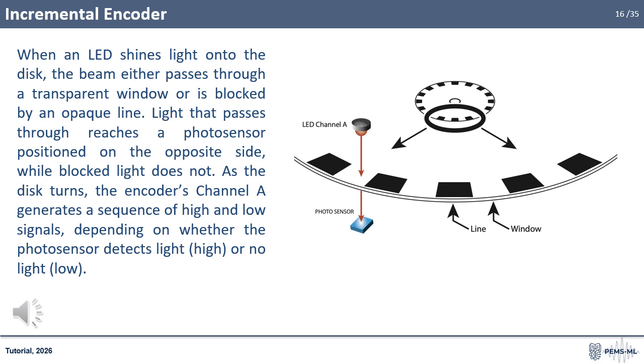To manufacture an incremental encoder, a pattern disk is produced. This pattern separates the disk into clearly defined sections, often using alternating opaque lines and transparent windows printed on a clear surface. When an LED shines light onto the disk, the beam either passes through a transparent window or is blocked by an opaque line. Light that passes through reaches a photosensor positioned on the opposite side, while blocked light does not. As the disk turns, the encoder's channel A generates a sequence of high and low signals, depending on whether the photosensor detects light (high) or no light (low).